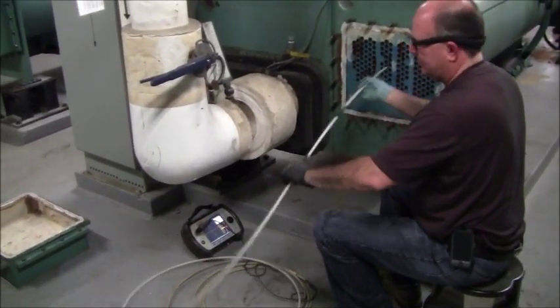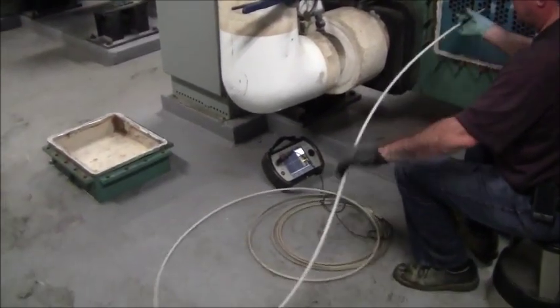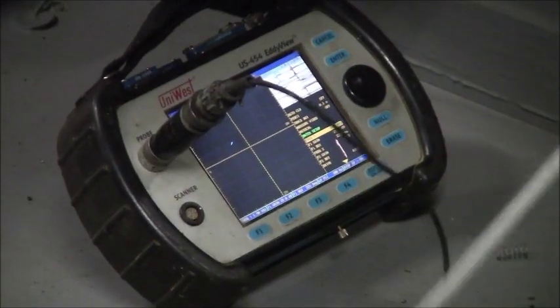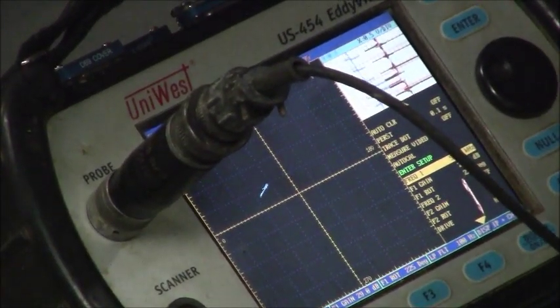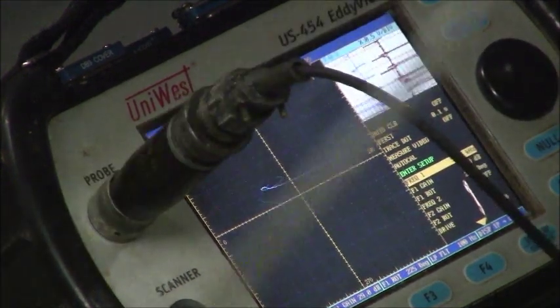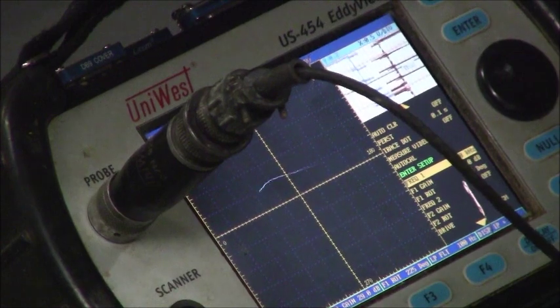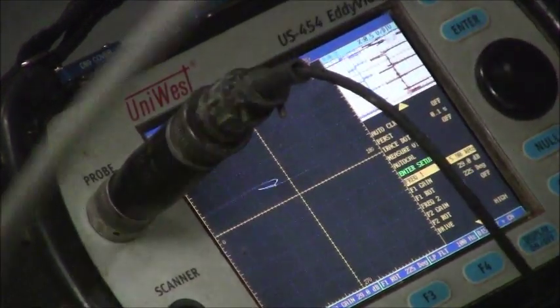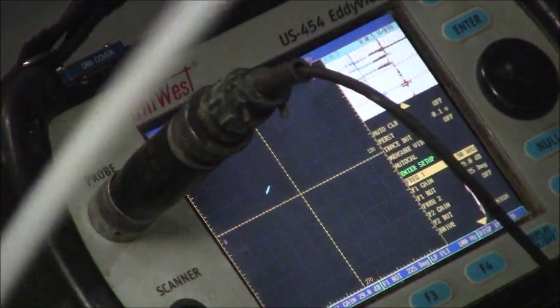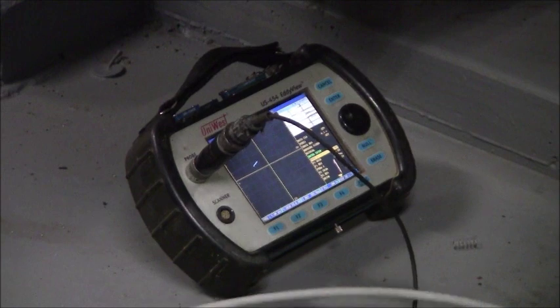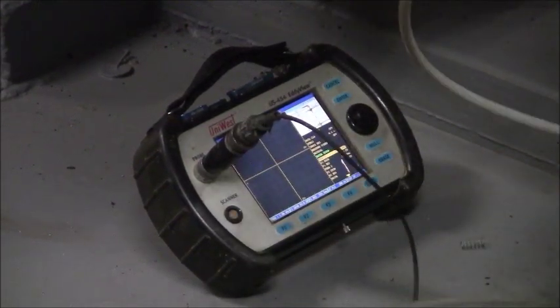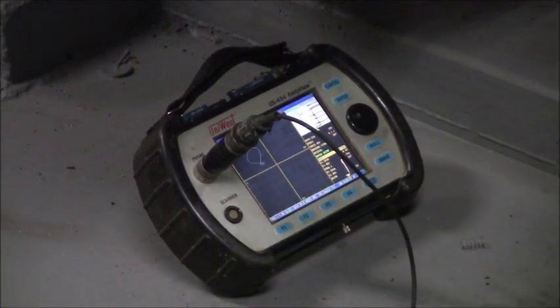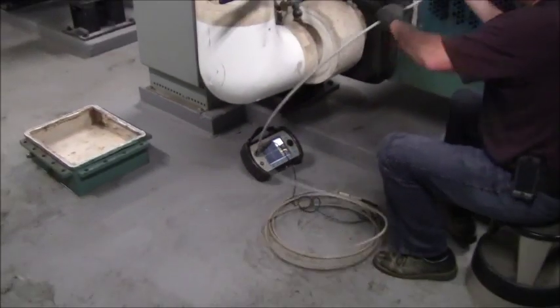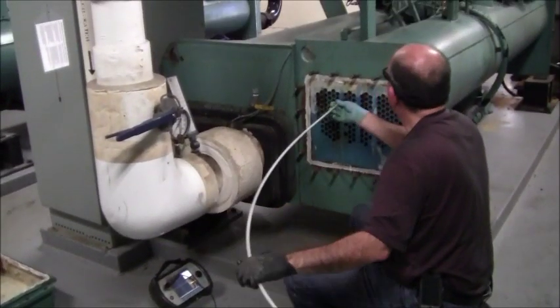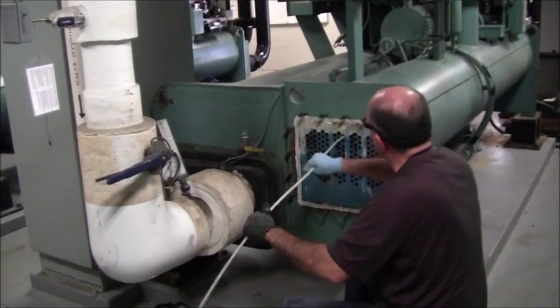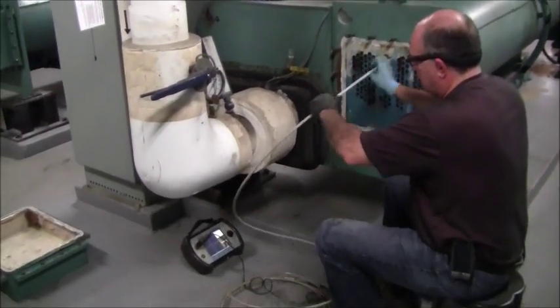So anyways, this is eddy-current testing for the machine. And he's looking at that dot to determine the thickness of the tube. And he can determine the thousandths of an inch of how thick the tube is. And also, as he goes through the tube supports, he can see the pattern that is being displayed on his display there. This particular machine that does the eddy-current testing is not exactly inexpensive. This is about $18,000 for one of these in order to do this eddy-current testing, which is used to determine the life expectancy of the tubes and what's happening with the tubes in your chiller. So that's pretty much what's happening here.